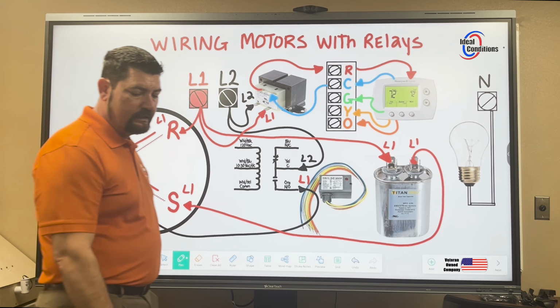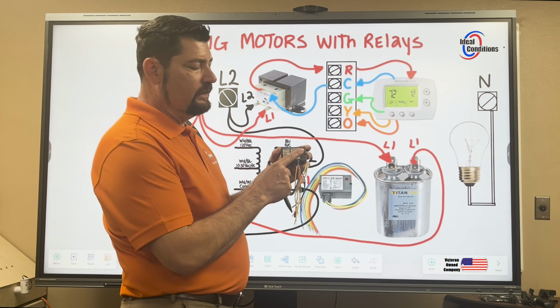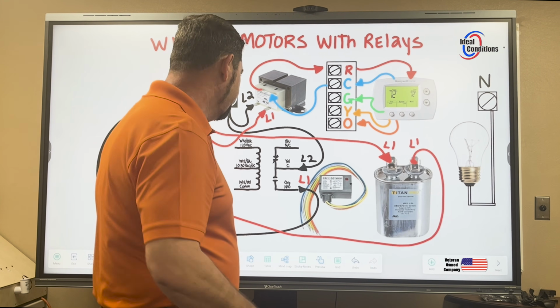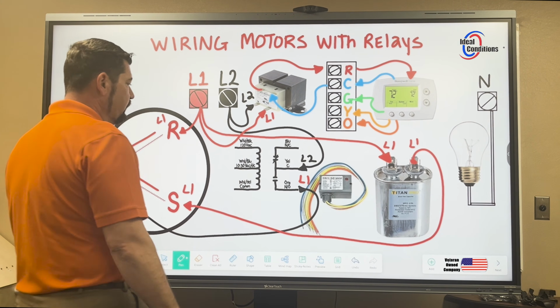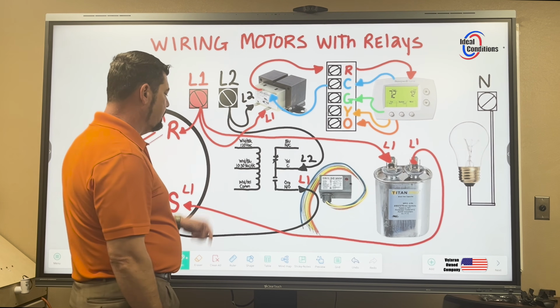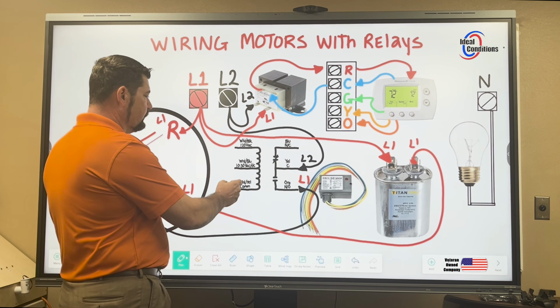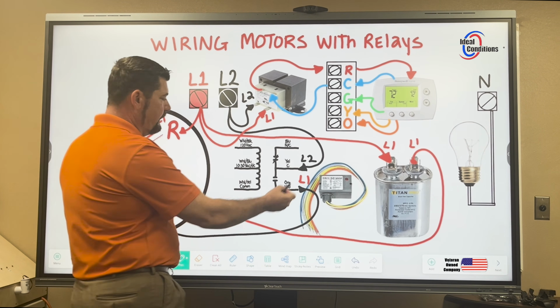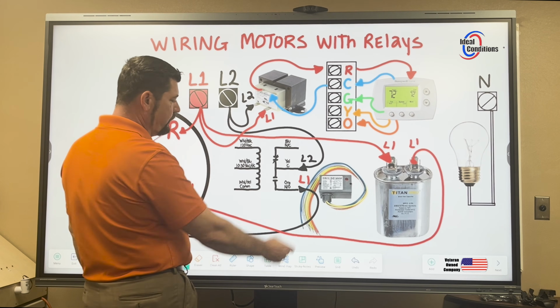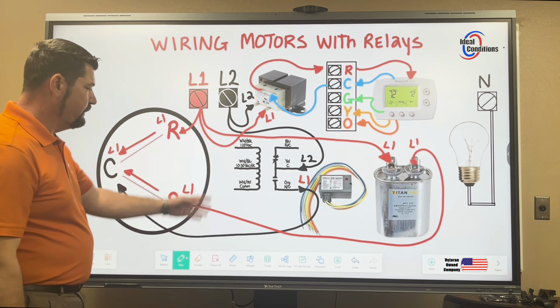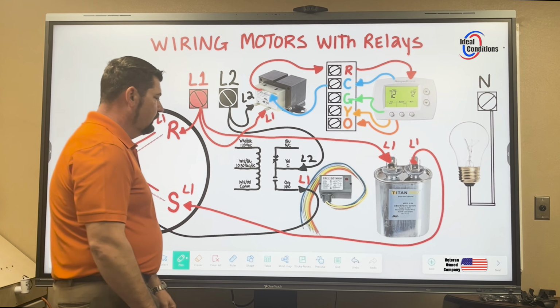Now, sometimes this light here, this little diode, can go bad. That doesn't mean the relay is bad. You can change it if you like. But if I didn't have my light on and I measured no voltage here, and I had 240 here, then there's something going on with control voltage. So let's go ahead and put 24 volts back.